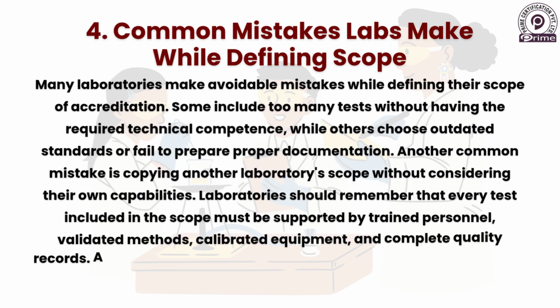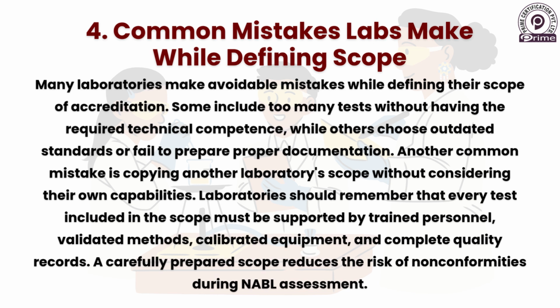Some include too many tests without having the required technical competence, while others choose outdated standards or fail to prepare proper documentation. Another common mistake is copying another laboratory's scope without considering their own capabilities. Laboratories should remember that every test included in the scope must be supported by trained personnel, validated methods, calibrated equipment, and complete quality records. A carefully prepared scope reduces the risk of nonconformities during NABL assessment.